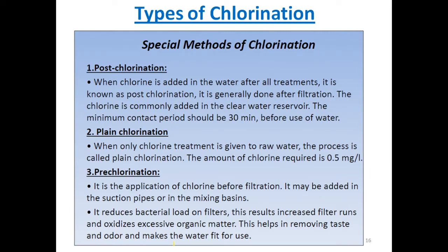Now, post-chlorination. What is post-chlorination? When chlorine is added in water after all the treatment, it is known as post-chlorination. It is generally done after filtration. The chlorine is commonly added in the clear water reservoir. The minimum contact period should be 30 minutes before the use of water. Post-chlorination is simply called chlorination.